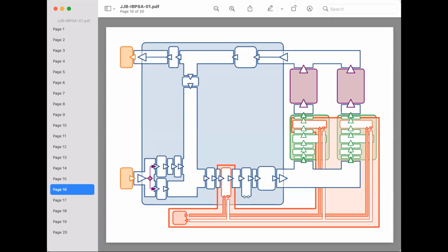So even in cases where there's systems of systems like this one with an air handler and multiple VAV terminal units providing air to different zones, it's relatively easy to build these graph models with appropriate tools. And the Semantic Interoperability Working Group has been developing these tools to build these models and test the standard while the standard is being designed. So in this case, you'll notice the hot water system contains boiler and preheat coils, preheat and reheat coils, where the coils are also parts of other systems. So these things can be nested.